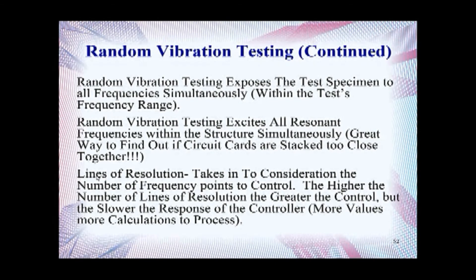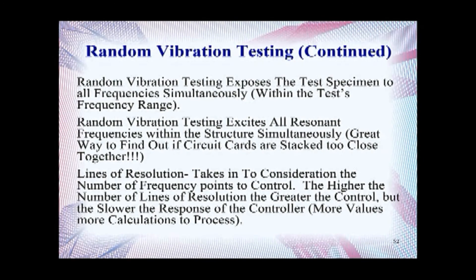As discussed in the previous presentation, Lines of Resolution takes into consideration the number of frequency points to control. The higher the number of lines of resolution, the greater the control, but the slower the response of the controller, because it has more frequency points to calculate. If you have a high number of lines of resolution, your controller will react more slowly and your real-time data will be delayed, which could potentially be dangerous because you would not be able to see issues on your vibe graph while running your tests, and it might be too late to stop a test.